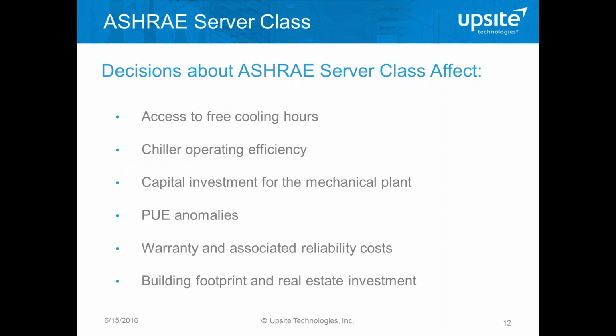That will translate, due to the fan affinity laws, which work against us as well as they work for us, to over 250% increase in fan energy, which could increase the total server energy of the data center by up to 25%. That increases our divisor of the PUE equation, so we get a better PUE, and we get a much higher total energy use. We can contrast that to A3 servers at 86 degrees, where we might see only a 3% energy increase, only 1/8 of the energy increase that we're seeing from A1 servers, which would be easily offset by all the savings we get from more free cooling, better chiller efficiency, from the other savings here.